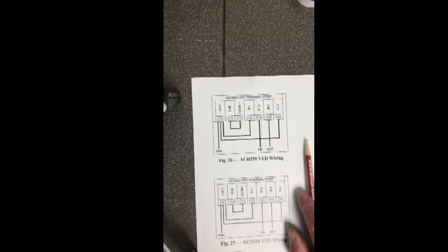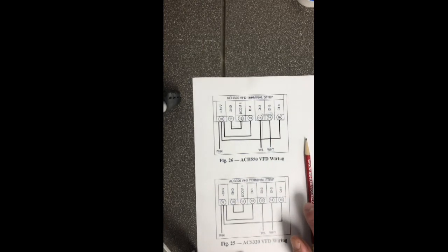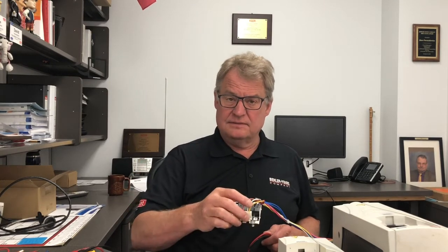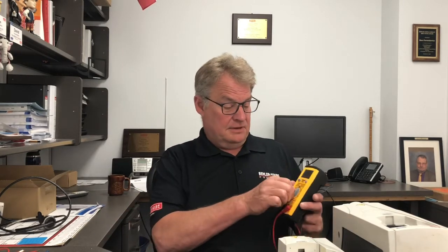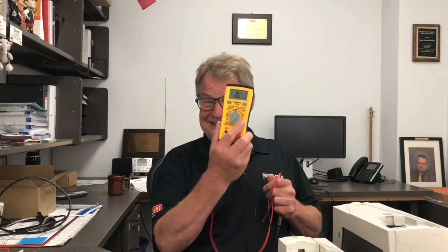So we would simply troubleshoot this with a meter. So if I have a call for cooling, meaning my thermostat's calling for fan, my heating has timed out, called for blower, or my cooling's on, so I have a signal going to this board, then I should have one of these relays closed. Now I can check that with my meter. I'm going to go to my meter, I'm going to put it on DC voltage.